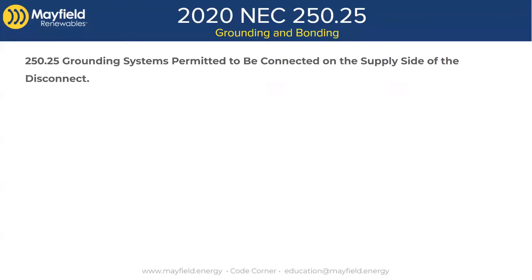In 2020, 705.11 — as many people working in solar know — is our supply side connections section, and that's a brand new code section as of 2020. What I would say is missing from that code section... well, it's awesome that we have a supply side connection section now. Prior to 2020, it was like: you can do it, but we're not going to tell you how. So go back into 230, go back into 250, fumble around, make it happen. Now at least we have some legitimate rules we can point to.